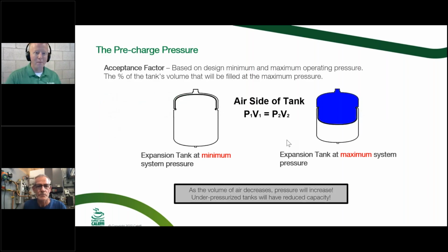What pressure should I set that tank to versus what the pressure is in your hydronic or your potable system? Yeah, so like we talked about the fill pressure, the math is in there. If you use that formula, you'll come up with what's called the acceptance factor. That's the factor, if you're doing bigger systems, that you use to size a compression tank or any tank. If you want to do the math, the quick calculators will be in there.